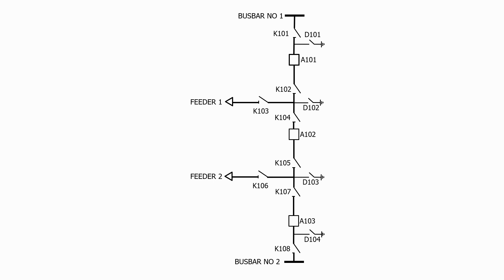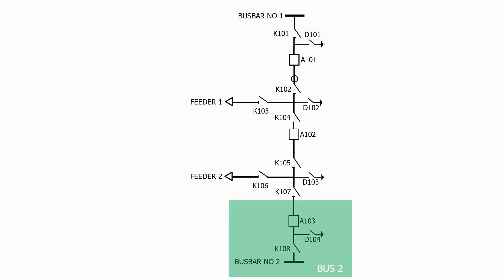Let's start with the busbars. We need a protection zone for busbar number 1, so let's place a current transformer for that zone in this location. We need a protection zone for busbar number 2, so let's place a current transformer for that zone in this location.